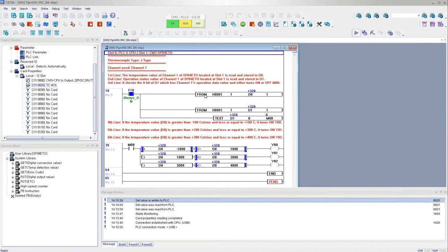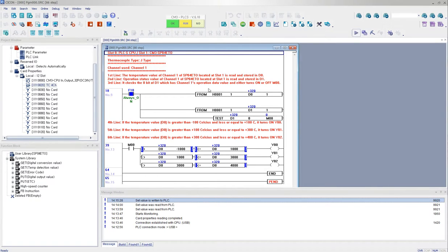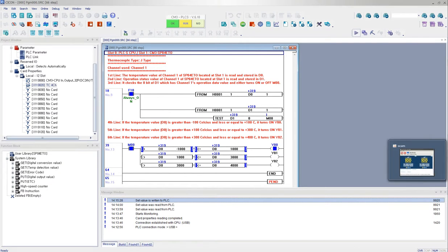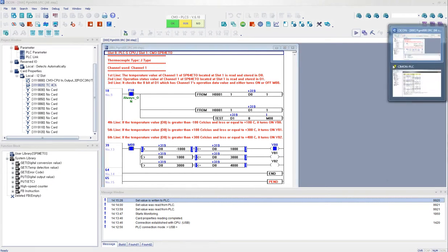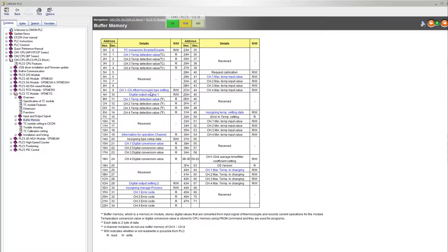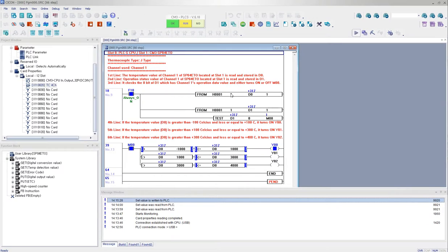So as you can see, the FROM command, I'm reading the data from the first module, the slot number 1. And I'm reading the buffer memory 1, which is channel 1, this value, the channel 1 temperature detection value. And I'm going to read that value and save it at D0.